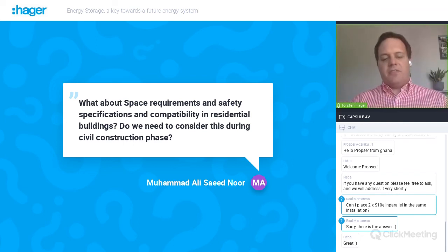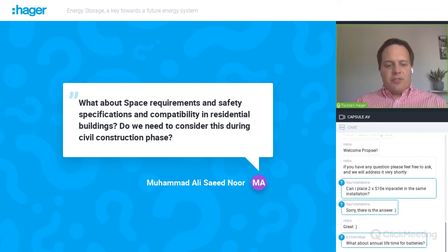I can give you the example of Europe. If you go to different countries, you have completely different requirements to respect, depending on local philosophy and local habits. For example, in Germany, if you install a PV panel on your rooftop, you take the cables, which are of course double insulated, and bring them to your cellar without any special measures, just normal cable trunking. Whereas in France, in the past, it was highly restricted, and you had to use fire-protected cable trunking and heavy equipment for the same installation.